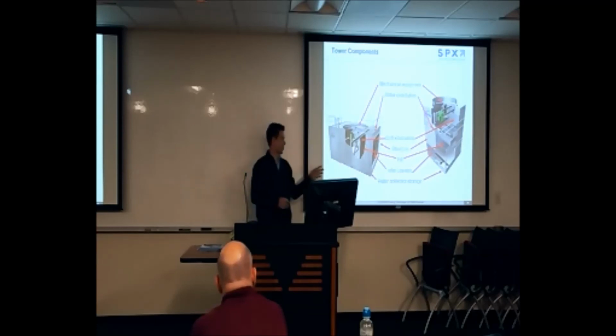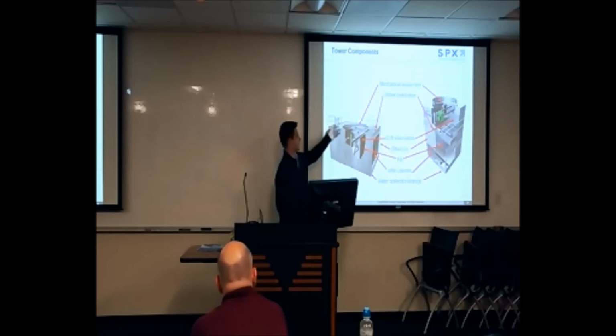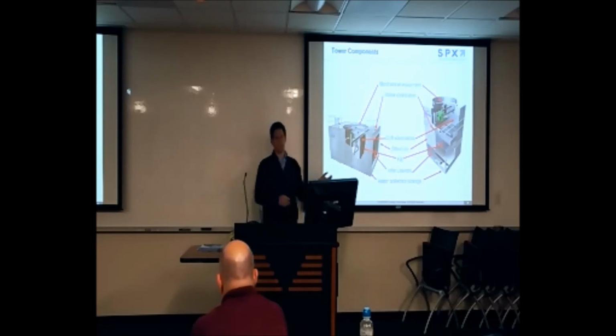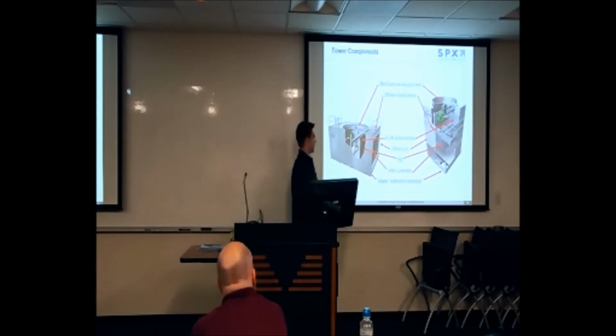These cooling towers are OSHA approved. All the maintenance guardrails we have are OSHA approved, but some consider it to be a confined space. So make sure that you lock out, tag out before anyone enters the tower. We also recommend that you don't run water over the fill while people are in there doing maintenance. A lot of maintenance guys will grumble at that and say, you're not going to get hurt from water, right? But that's another precaution to keep in mind: to not be in there when the tower's running at all, both mechanically and hydraulically.